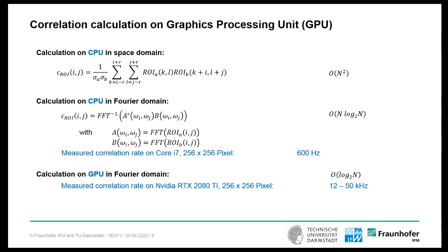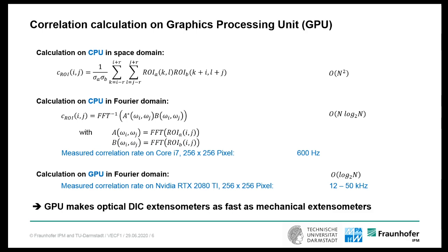A graphics processing unit, GPU, has thousands of processor elements. Therefore, it's a log-n problem, which means acceleration of two orders of magnitude. There we achieved a correlation rate of up to 50 kHz. This means the GPU makes optical DIC extensometers as fast as mechanical extensometers.